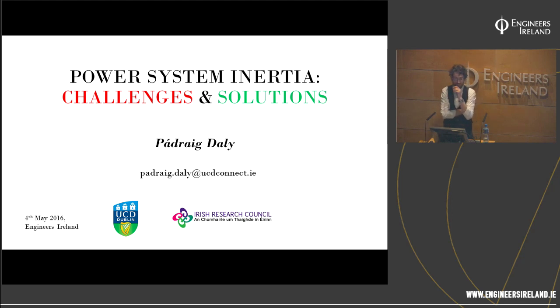Well, statistically, it's actually superior, because if you're dependent on a small number of generators to respond, the likelihood of one of them not responding, and the impact that would have on the system frequency, is huge. Whereas if you have distributed sources, all else being equal, which is not, but if it were, that's a superior form of reserve.